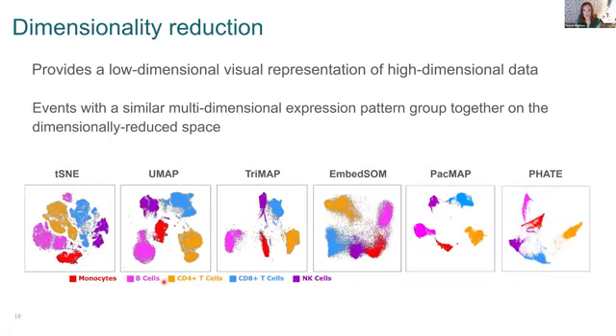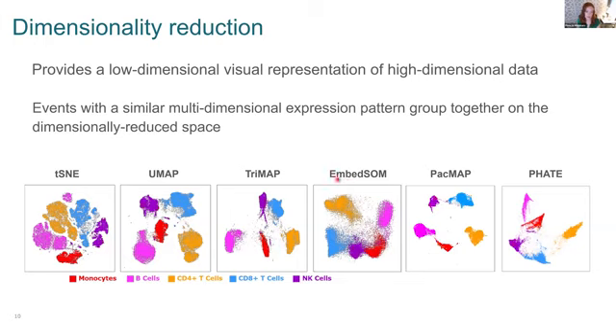Going back to dimensionality reduction — this is primarily for data visualization. We have a number of these available in FlowJo: t-SNE, UMAP, EmbedSOM, Trimap, PacMap, and PHATE. t-SNE and UMAP are probably the most well-known. t-SNE is popular because it was one of the first dimensionality reduction tools used in flow cytometry and it flattens data really nicely, giving good local structure — we can see the resolution inside islands very well.